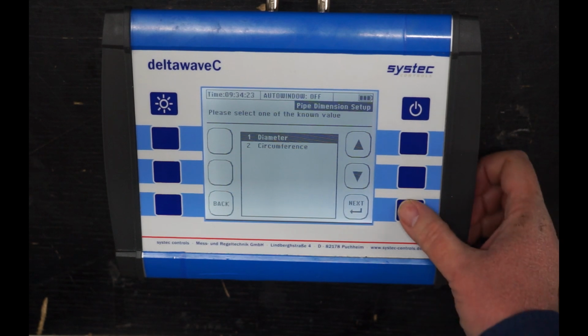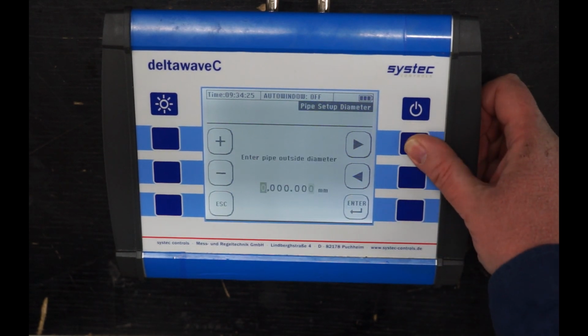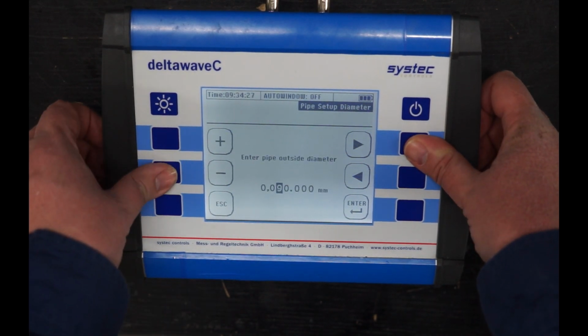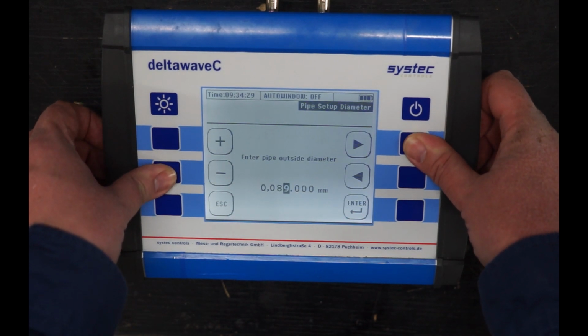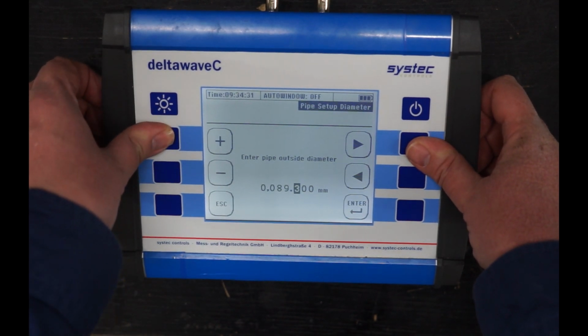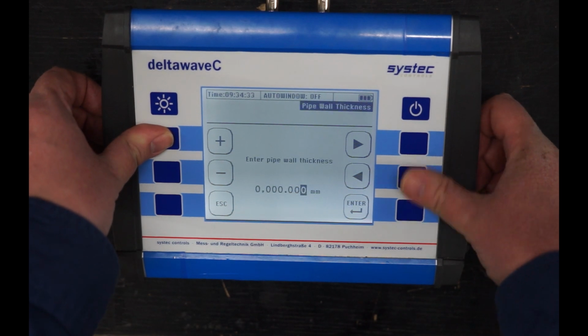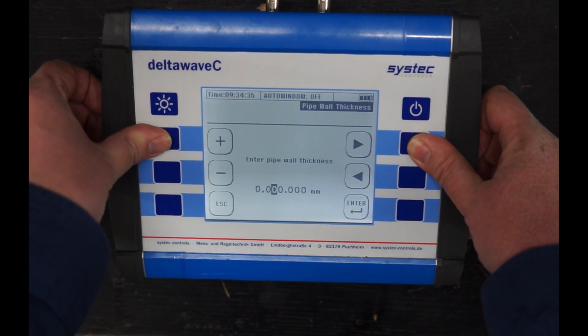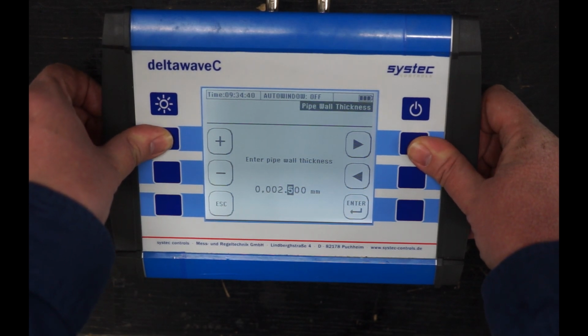To start the measurement, enter either the diameter or the circumference of your pipe. In this case, 89.5 millimeters. Then deltawaveC will ask you for the wall thickness of your pipe. In this example, the wall thickness is 2.525 millimeters.